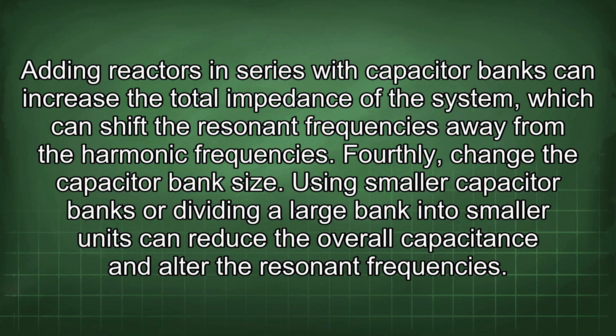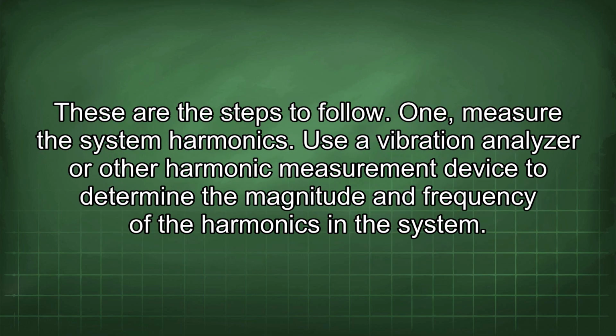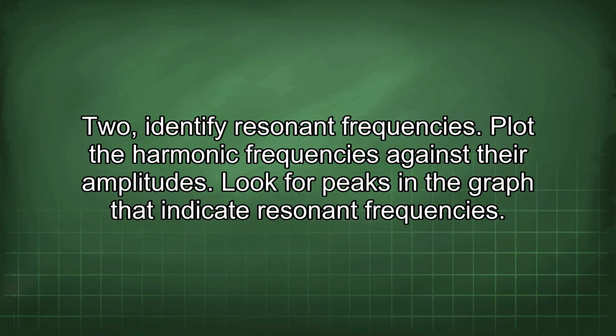Fourthly, change the capacitor bank size. Using smaller capacitor banks or dividing a large bank into smaller units can reduce the overall capacitance and alter the resonant frequencies. These are the steps to follow. 1. Measure the system harmonics. Use a vibration analyzer or other harmonic measurement device to determine the magnitude and frequency of the harmonics in the system. 2. Identify resonant frequencies.